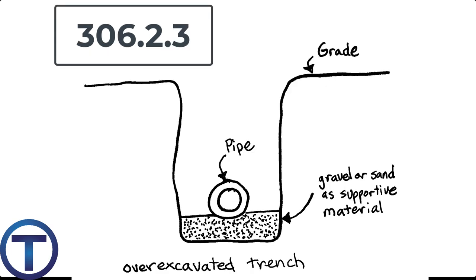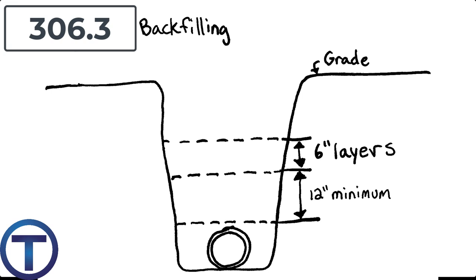306.2.3 soft load bearing deals with organic soils — say you dig it up and it's real light and fluffy, not strong enough to support pipe well, and it's possible they could create a belly. We remove that earth and refill with something supportive. 306.3: when it's time to backfill, the requirement is to fill in above the pipe 12 inches first — that protects the pipe as we're compacting. Then above that, we fill in with 6-inch lifts, compacting each 6 inches until we get to the top. It's really important to compact properly rather than pushing all the spoil pile in at once.